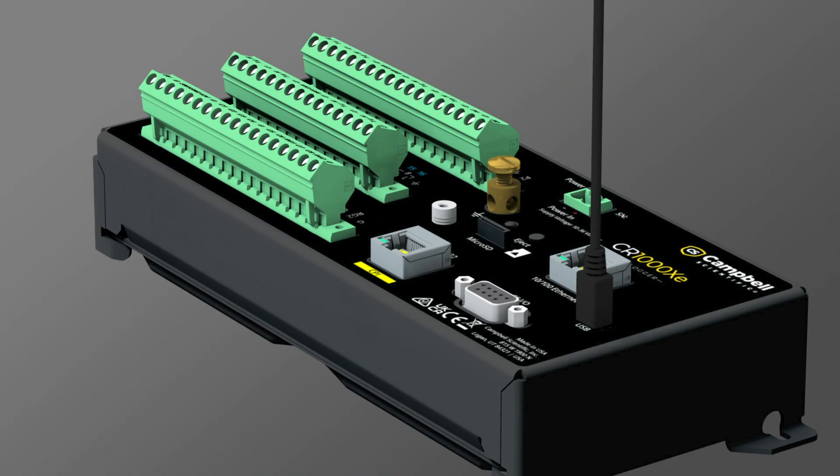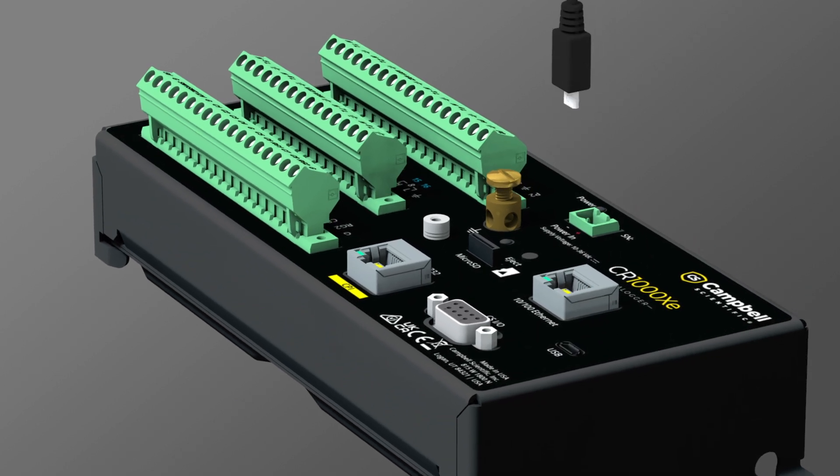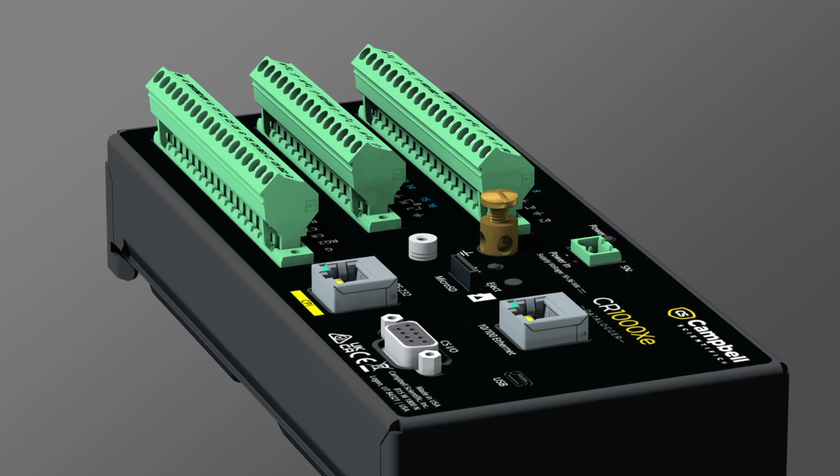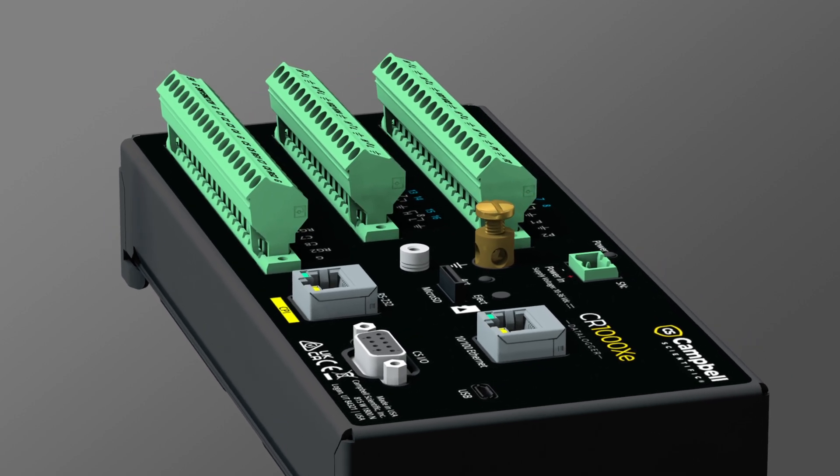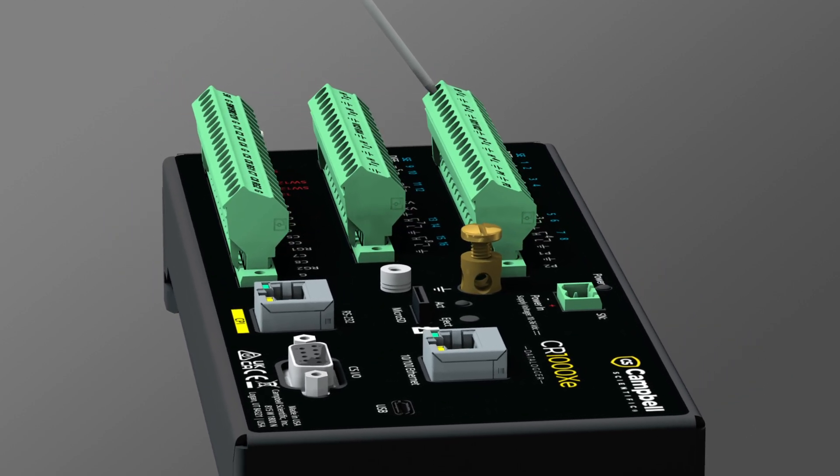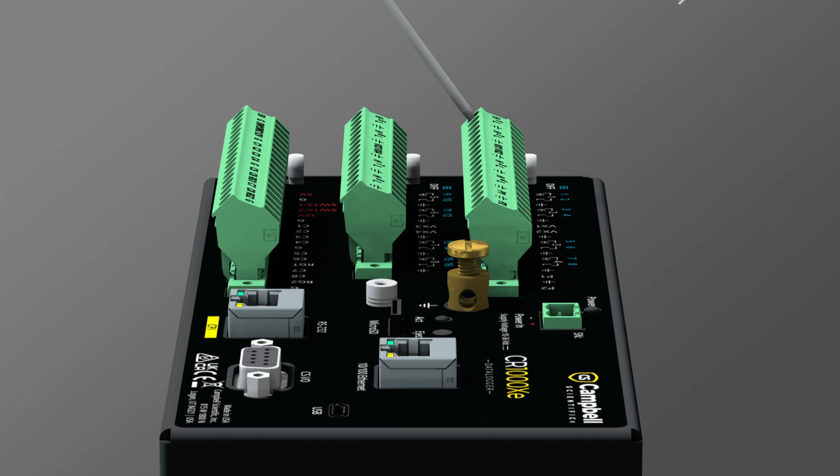It's good practice to remove power from the data logger before making changes to the wiring. Disconnect the USB cable. I attach my wiring to the data logger by opening the wiring terminals and inserting the wire, taking care to ensure the terminal clamps down on the conductor itself, not the insulation or colored part.